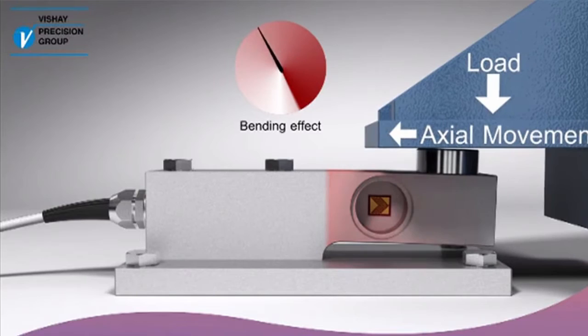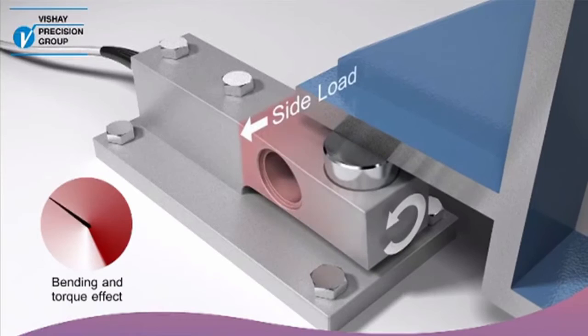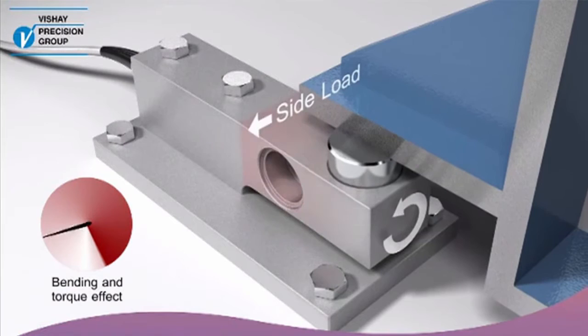The side loads can be in any direction, caused by agitation, wind loads, or the flexing of structural supports and piping connections. In addition to bending errors, the load cell is now subject to twisting forces, which result in additional torque errors.